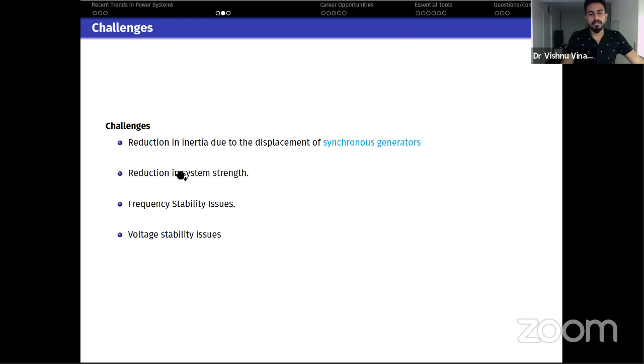The other important factor that is associated with the transition of the power systems is the reduction in system strength. So basically, system strength means the amount of fault current that is available at any particular point of the network. For example, let's say we have the Indian power system, and we take a particular substation, for example, in Mumbai, and we have a certain amount of fault level. If we replace all the synchronous generators from the network, specifically the synchronous machines that are closer to the Mumbai substation, the fault level in that particular area will reduce.